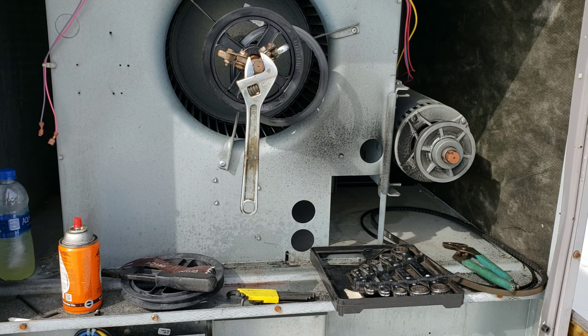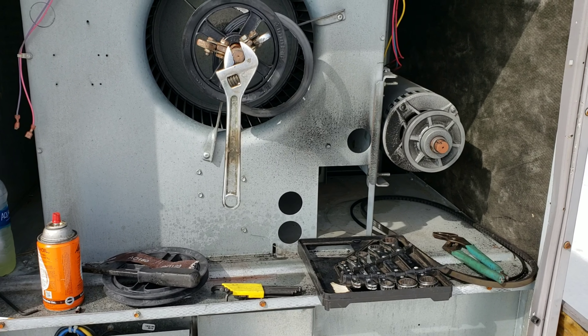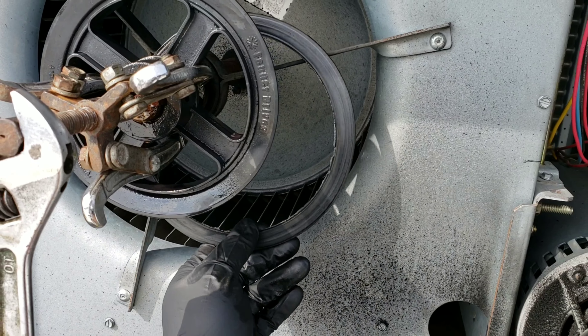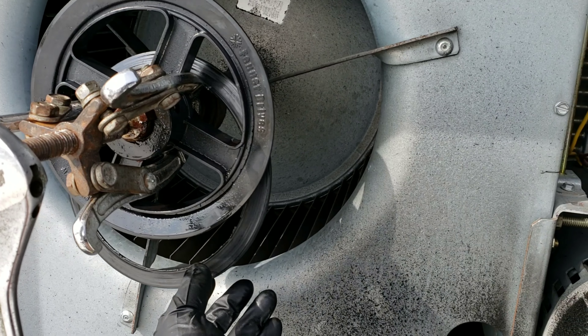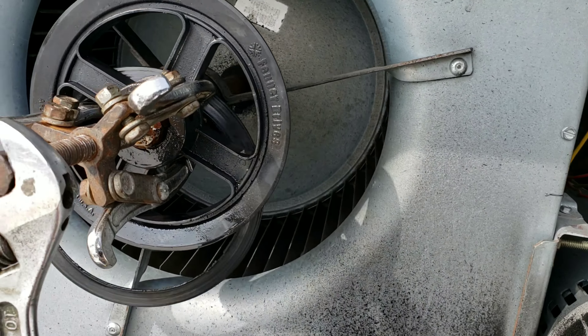What's going on, Thompson's Kennels HVAC life. I'm gonna tell y'all again, I had the right tools to do the job. Working on the Carrier unit — I already replaced one cracked driven pulley on this same job site, and this is another one. I mean, Carrier, look at this — this is just crazy.